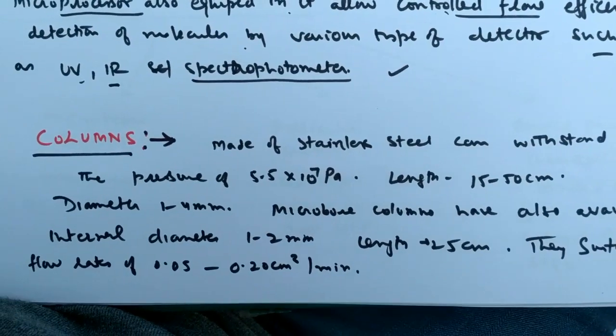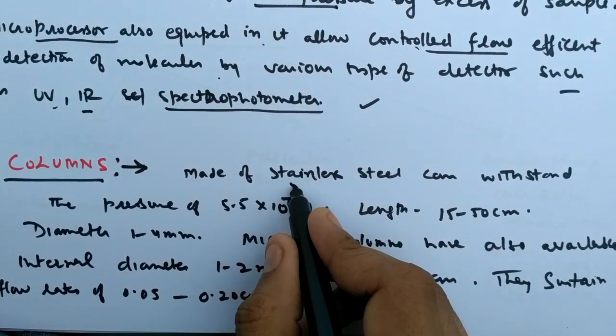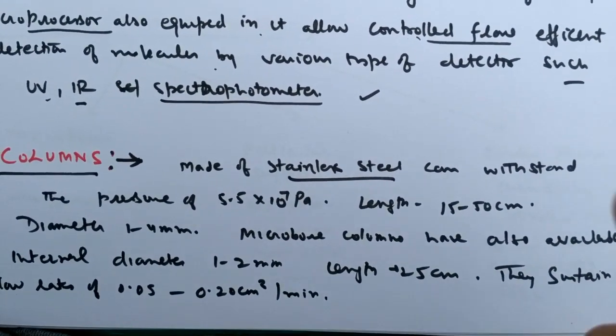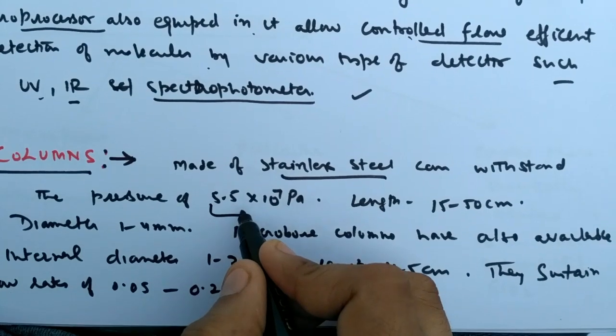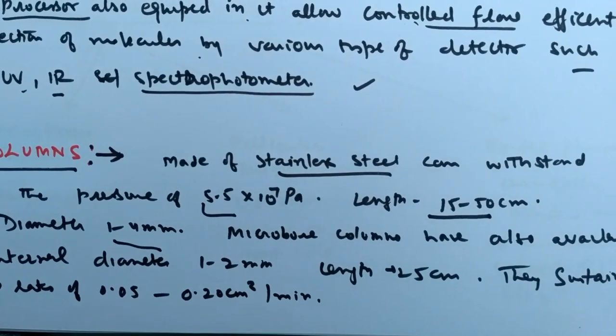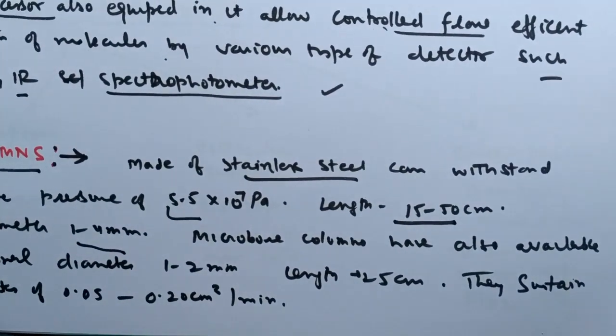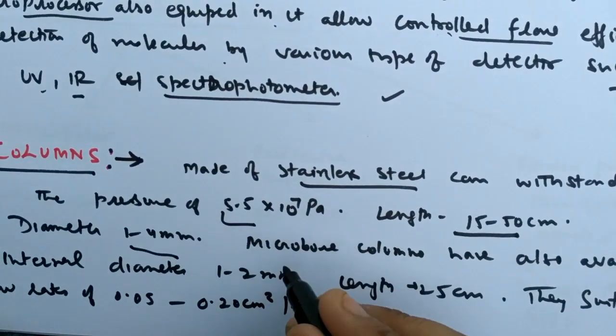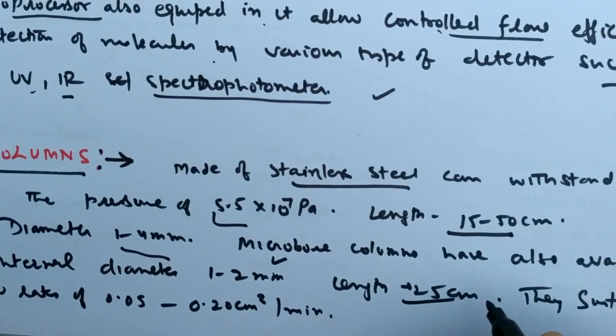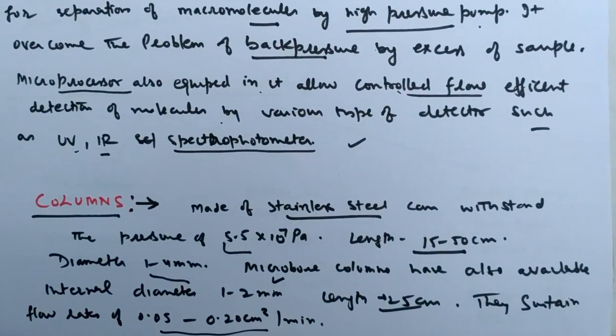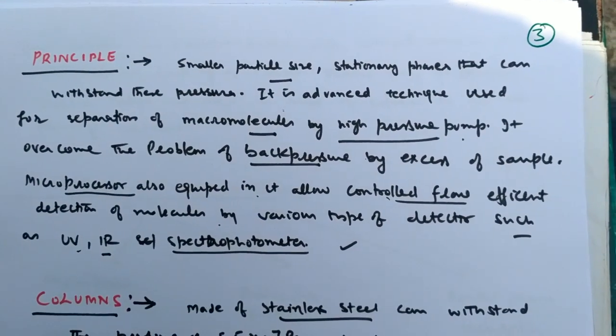The column is the stationary phase and it is made of stainless steel, which is a very solid alloy that can withstand pressure of 5.5 × 10^7 Pascal, having a length of 15 to 50 centimeters and diameter of 1 to 4 millimeters. Micro bore columns are also embedded internally and have a diameter of 1 to 2 millimeters and length of 25 centimeters, and they can sustain this level of pressure.